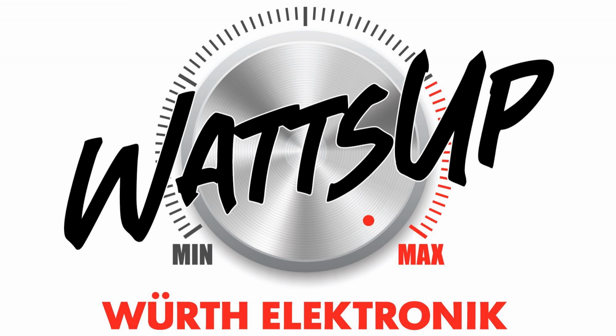Clear means that every second, because I set the dwell time at 1 second, it's measuring. It's an FFT receiver, so the measurement is really fast. In 1 second, I'm measuring from 150K to 30 mega. I don't care about the peak detector because the standard asks me to measure with the average detector. So the limit is with the average. Some of you, if you have an old analog receiver, have to do the measurement with peak, scan all the band, and then go back with the quasi-peak detector. This doesn't have to happen with EMSER.